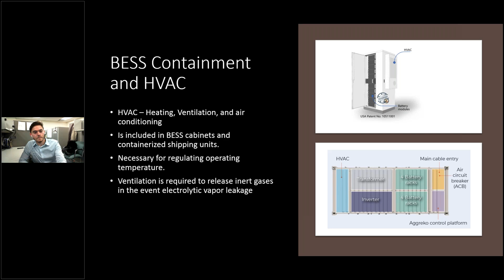Undersizing the cooling system can lead to batteries overheating. Oversizing the cooling system can lead to short cycling and large air temperature swings when the unit turns on and off.